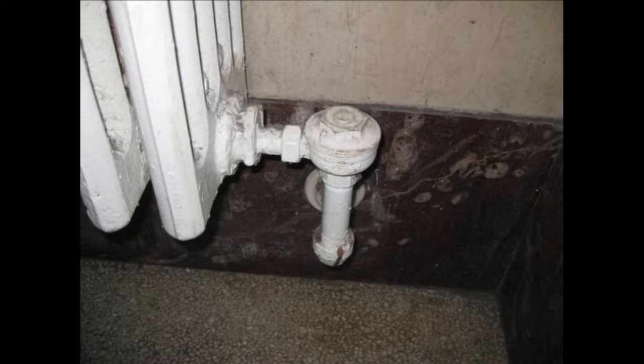So now the alcohol is going to condense inside, and the atmospheric pressure of the air on the outside of the bellows is going to cause the bellows to scrunch up. At the bottom of the bellows, there's some sort of a pin that goes into a seat. So this is normally open, and steam pushes the air through the radiator trap because before a radiator trap can trap steam, it must vent air. It's going to push air downstream, or it'll leave the system through either an automatic air vent, or the vent line on a condensate pump or a boiler feed pump receiver.